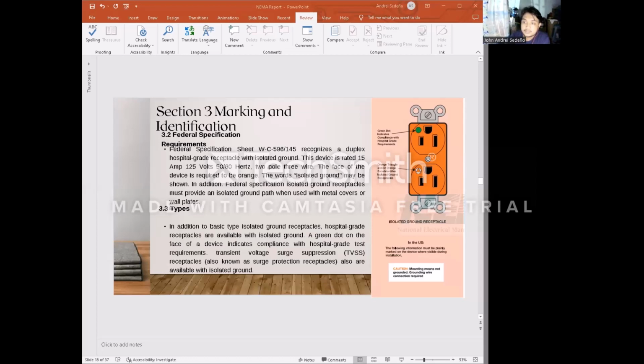Now, what color is an isolated ground receptacle? Isolated ground receptacles are required to be identified by an orange triangle located on the receptacle. Now, where does the isolated ground terminate? It should terminate on the same ground bar as the equipment ground bar in your situation, since this is the source of your separately derived system.